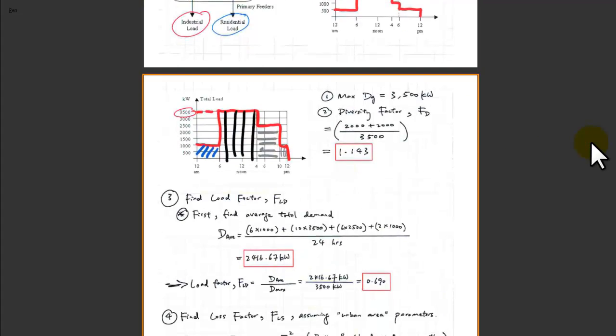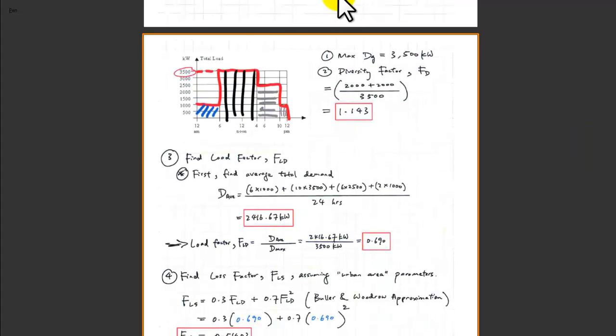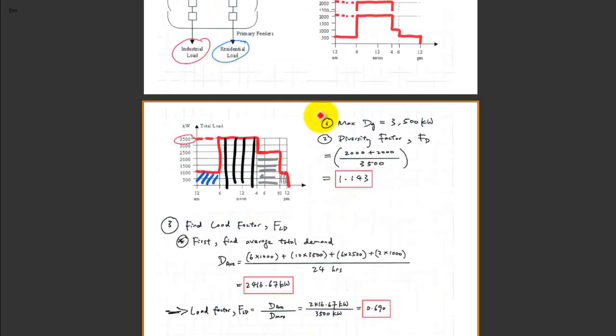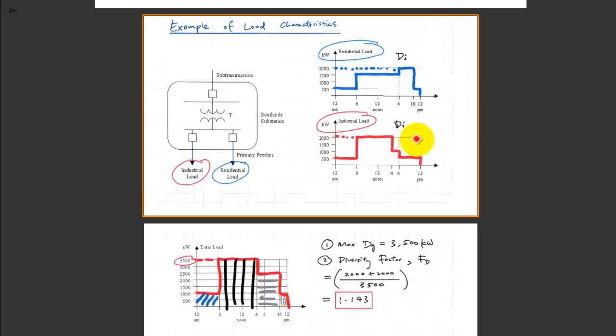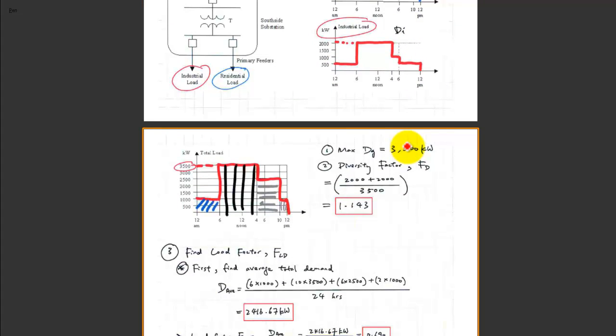The next figure shown here is the coincidental demand, which is diversity demand D sub G. As you can see, this is the combined version of those two feeder loads instead of individual curves. So right away, if you were asked to compute the maximum diversity factor, you have to use this figure and find the maximum value throughout that 24-hour period.